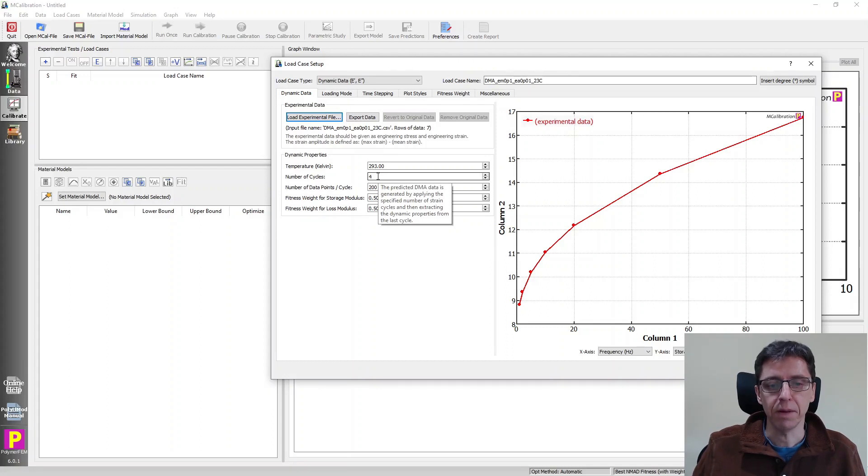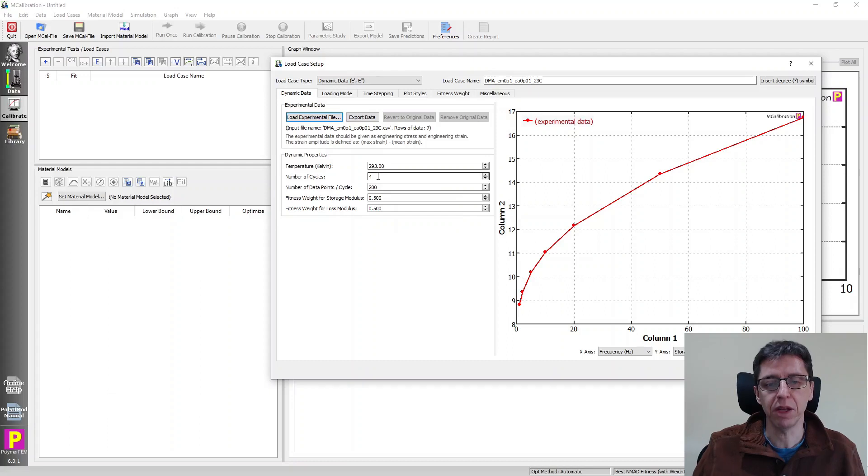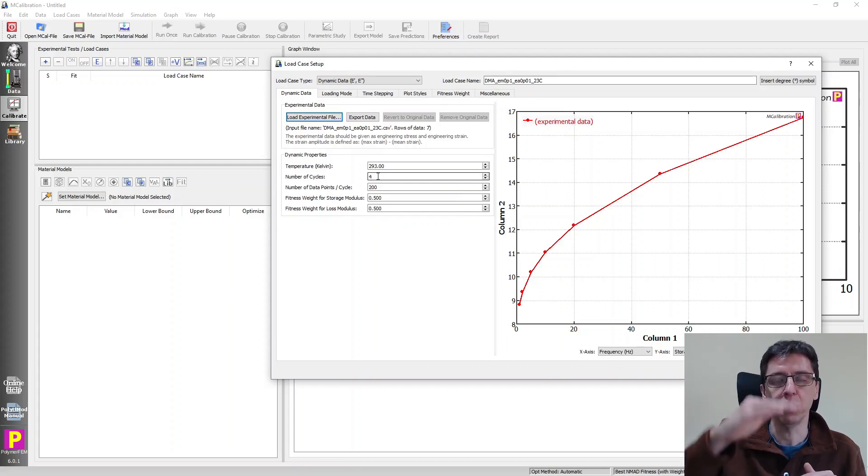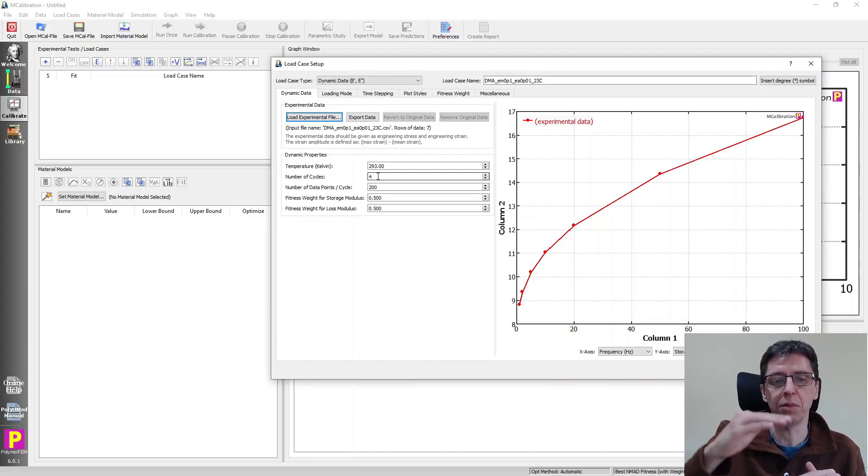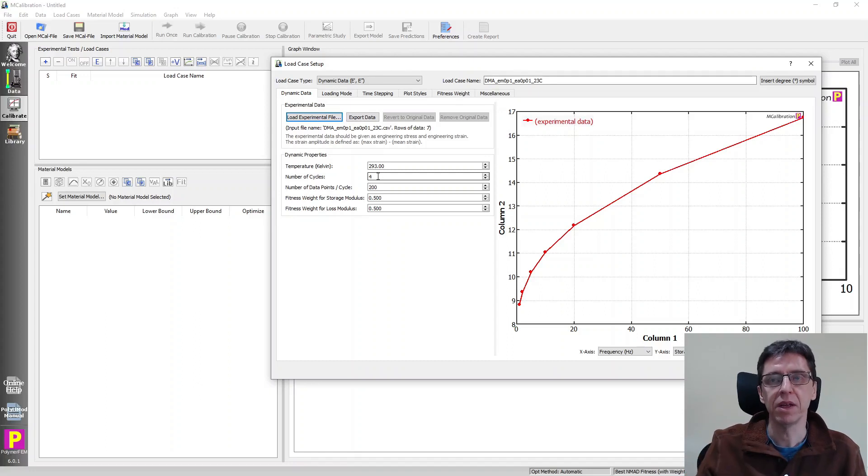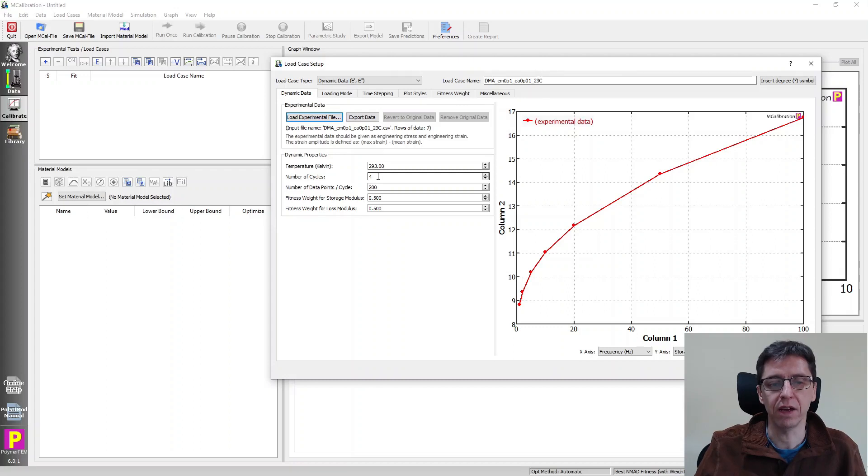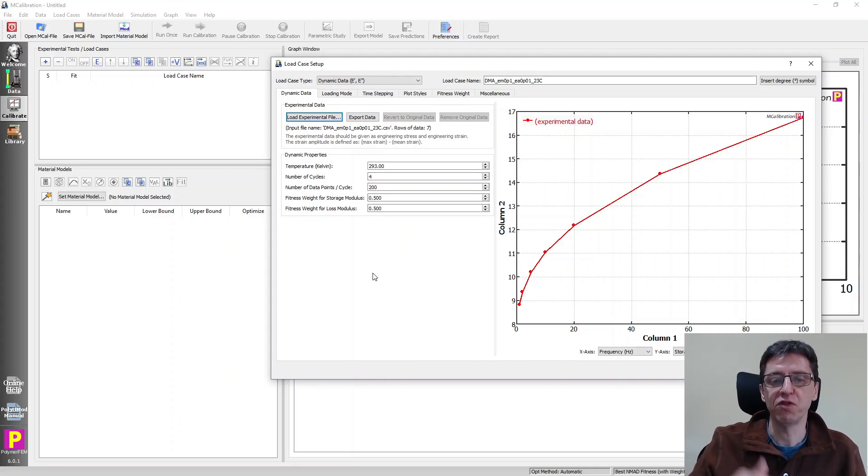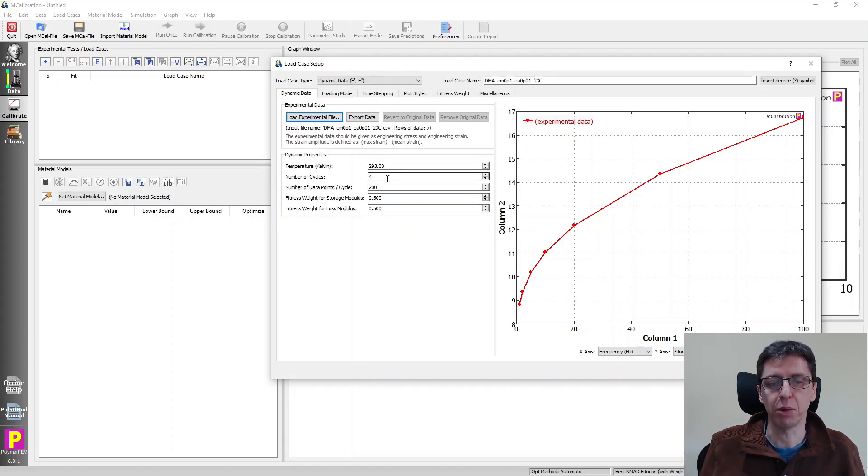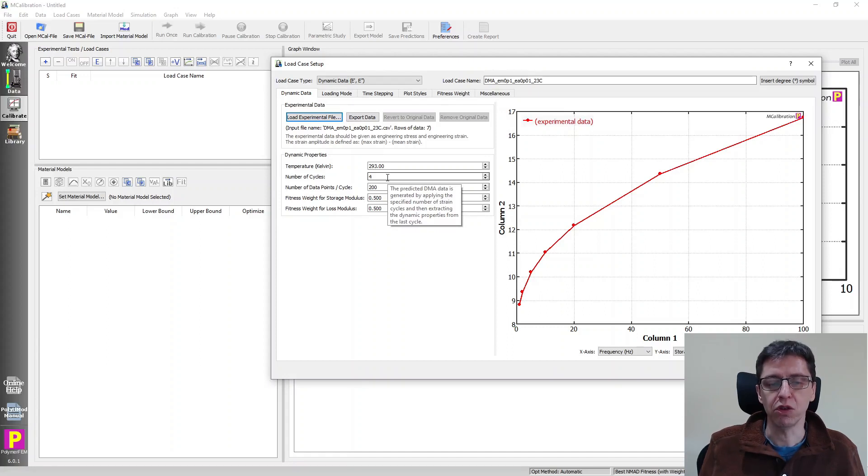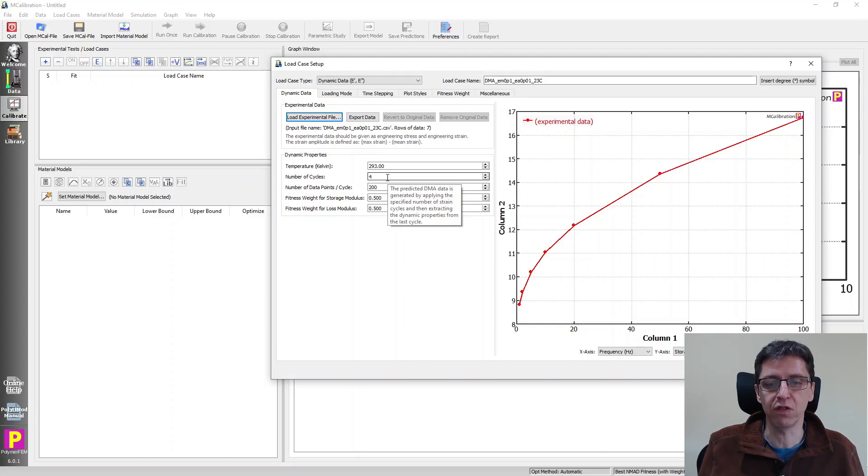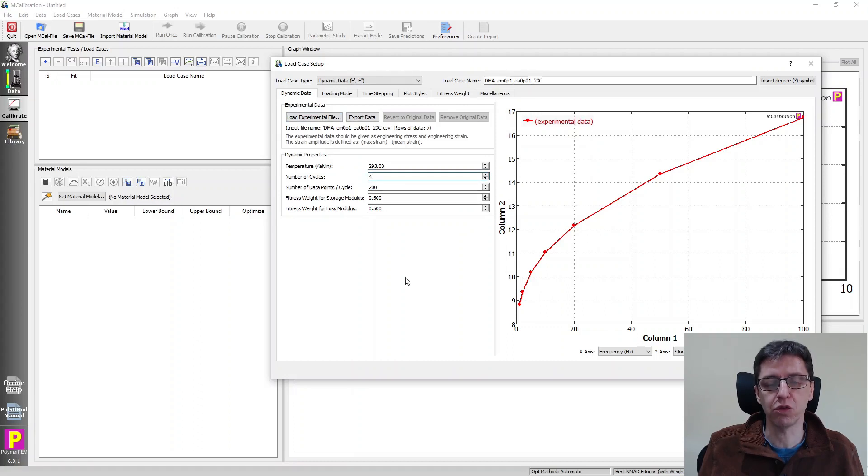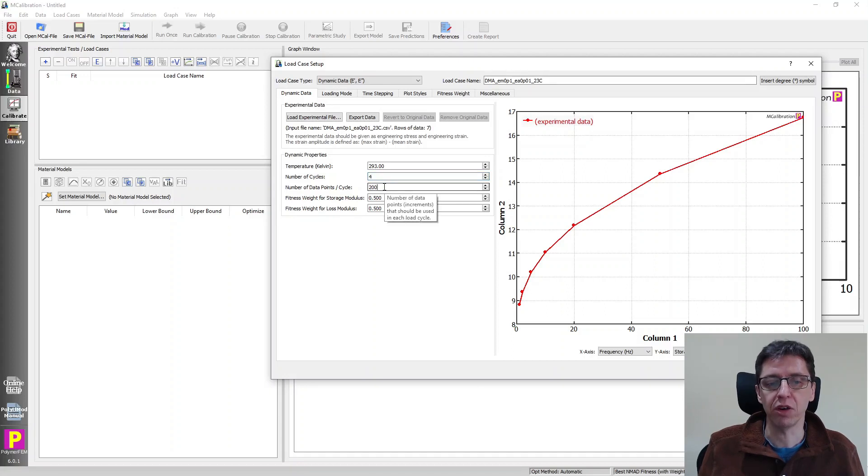So the way it works, I guess we can mention it in the DMA machine. When you run a DMA test, the test system will cycle between the strain with a given frequency and strain amplitude. But it extracts the dynamic data gradually as it changes the strain frequency or amplitude. In MCalibration, what we do, we specify the number of cycles that will be applied before it takes the last cycle and extracts the dynamic properties, the storage and the loss modulus from it. And it's not using the first cycle because it takes a while sometimes to reach steady state. So you want to have a steady state viscous response. And that's where you can specify here how many cycles should be applied before it tries to extract the storage and the loss modulus.